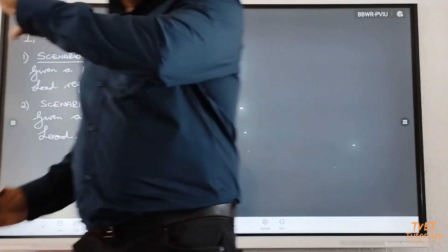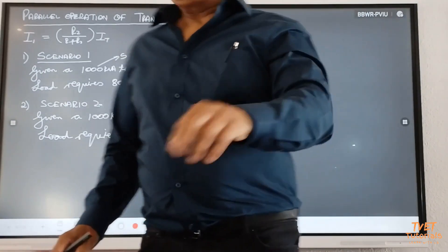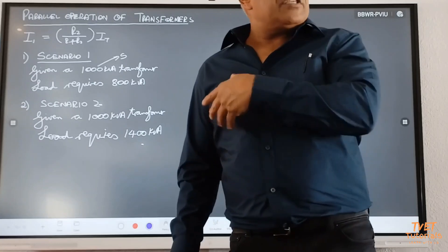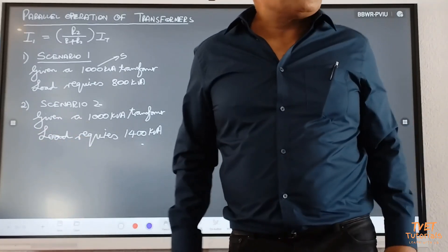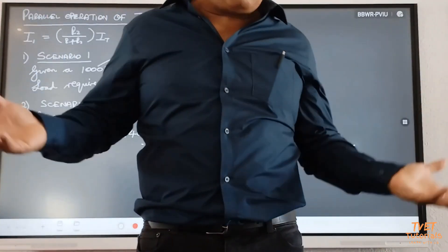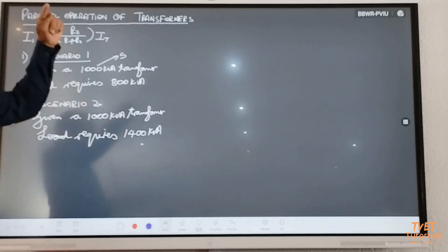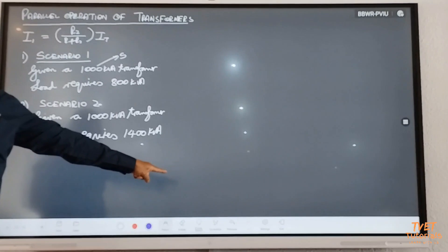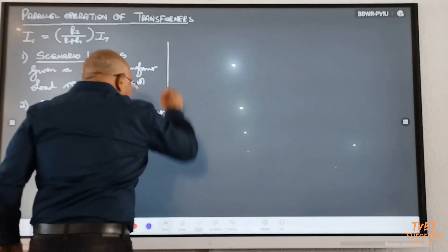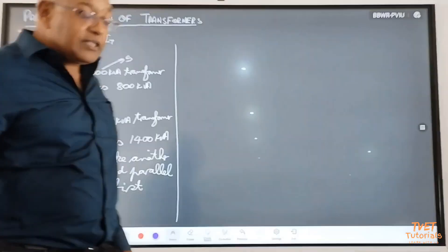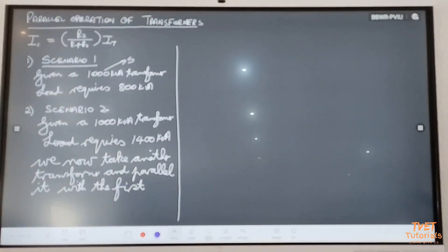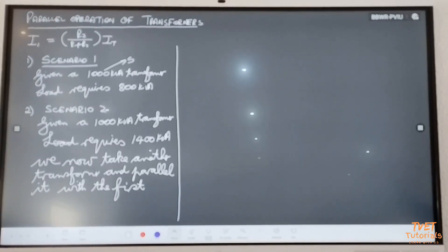What do we do? We take this transformer away and buy a 1,500 kVA transformer. But the municipality has no money to buy a transformer. So you go into your stores and see what transformer is available. We need to parallel another transformer so that we can supply this load. If you find a transformer rated at 500 kVA and above, the two transformers combined will give 1,500 kVA. The consumer wants 1,400 kVA — this is where we come to parallel operation of transformers.